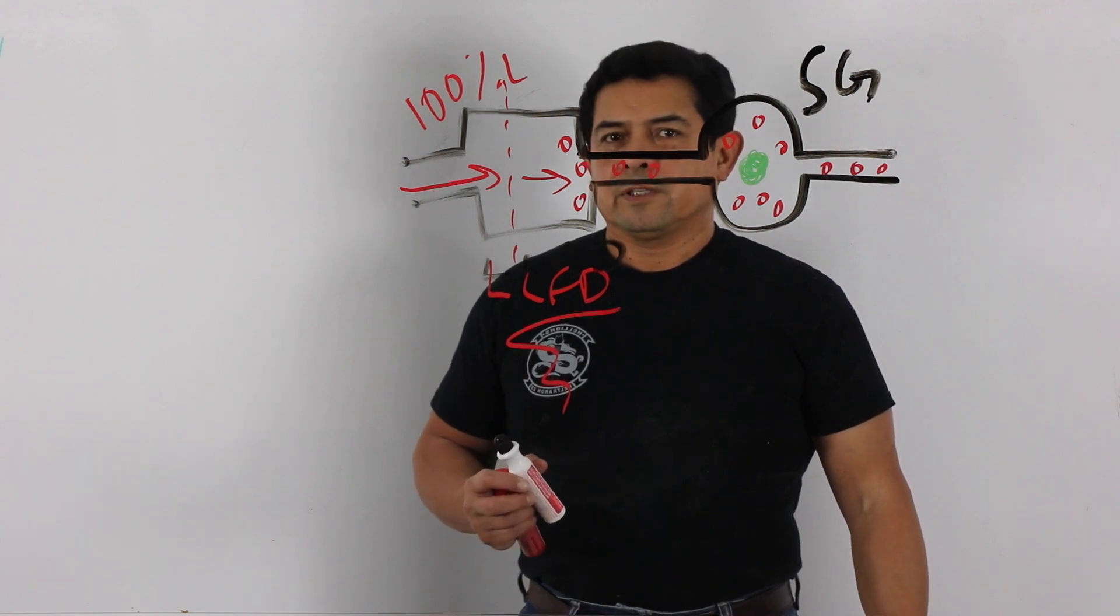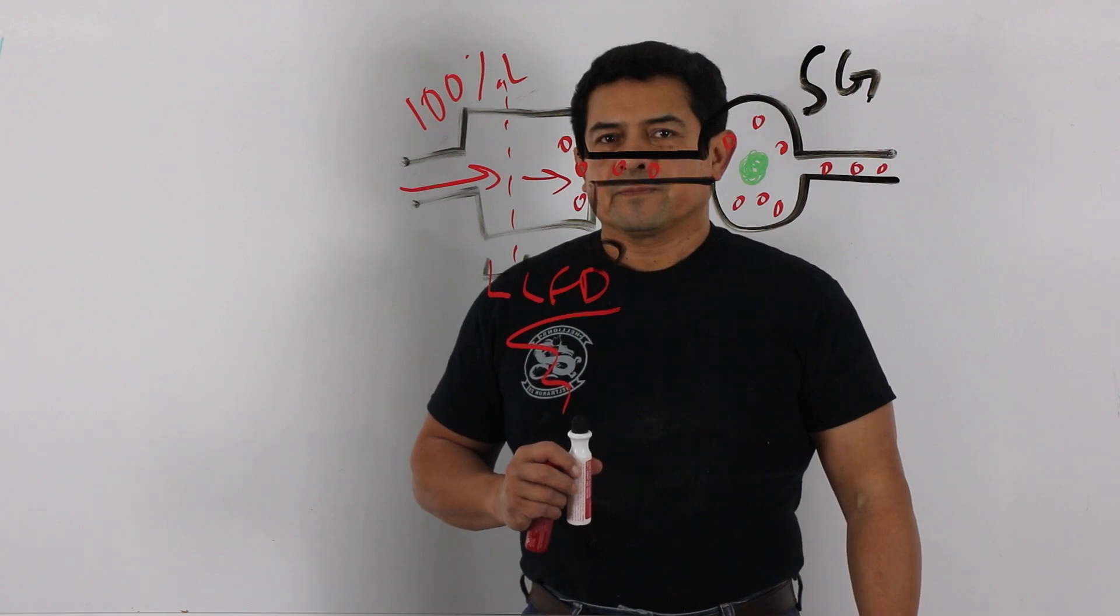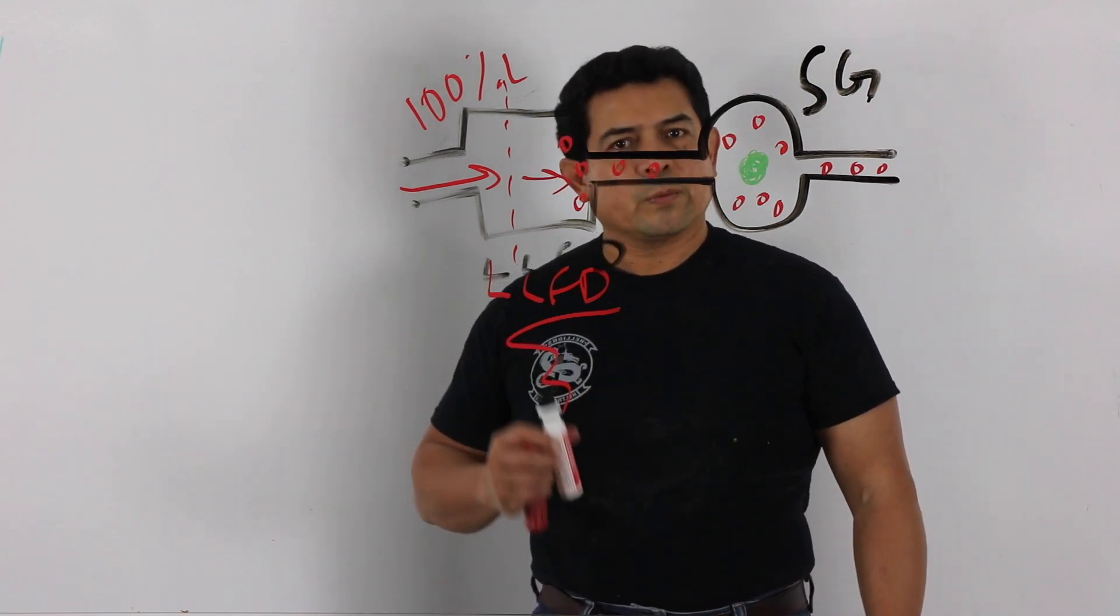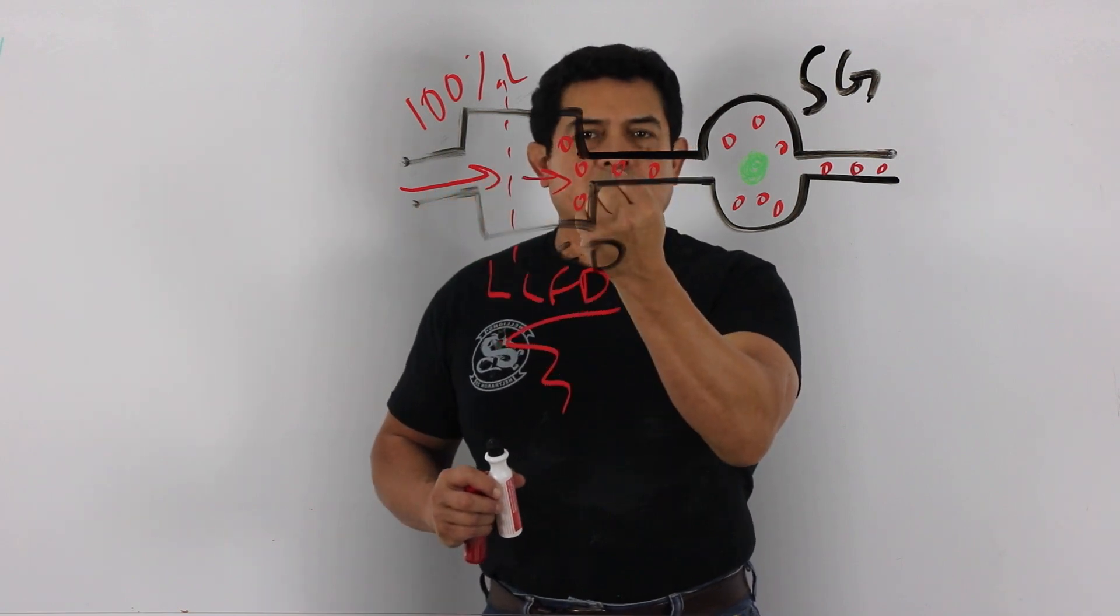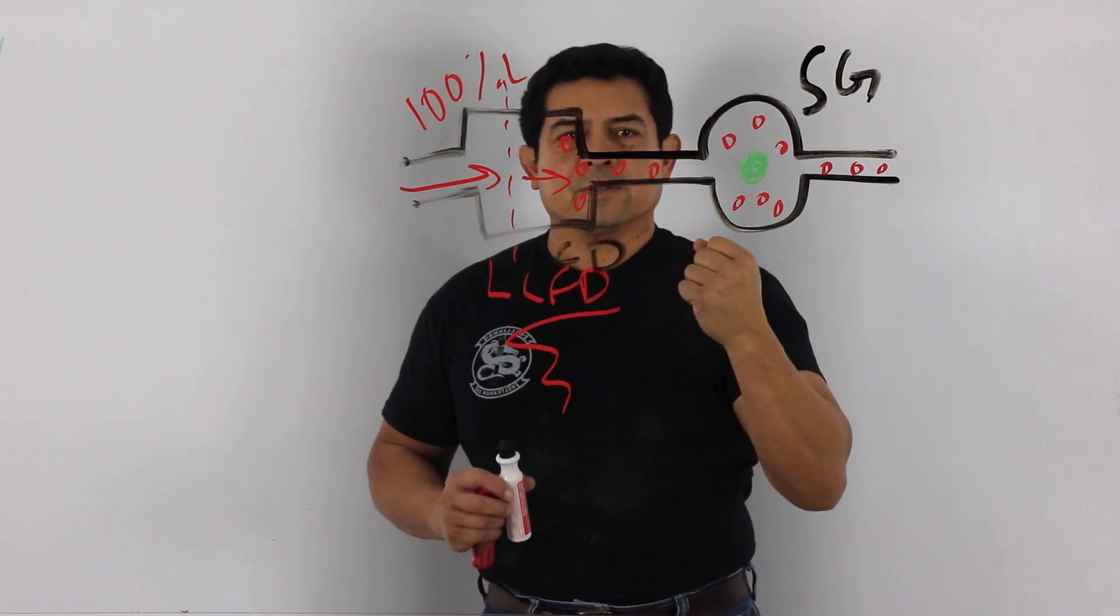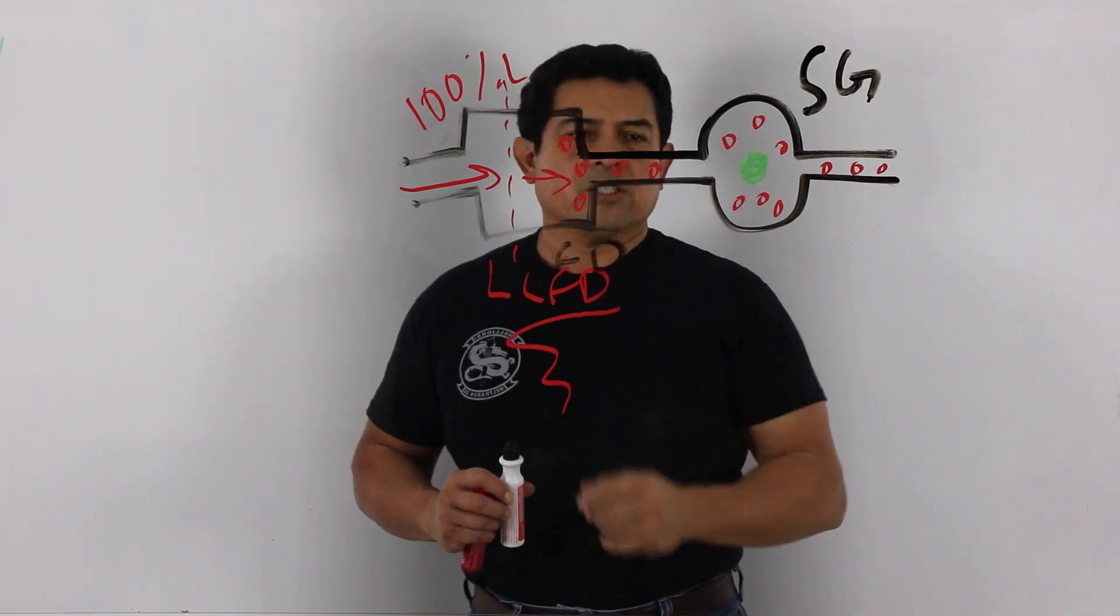So what are you going to do? Well, how do you know that this dryer is clogged up? If you remember, one of the things that we have said is that you touch one side of the dryer, you touch the other side, if there's a temperature difference, then you know that this dryer is clogged up and it needs to be replaced.